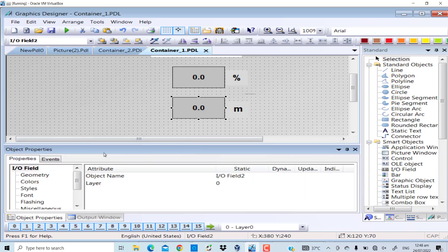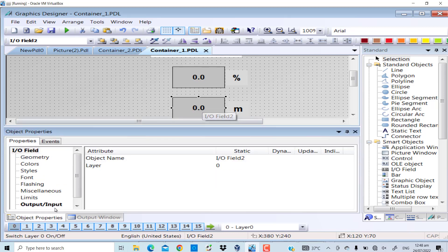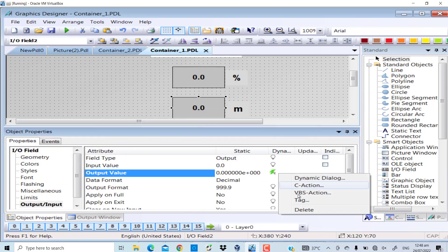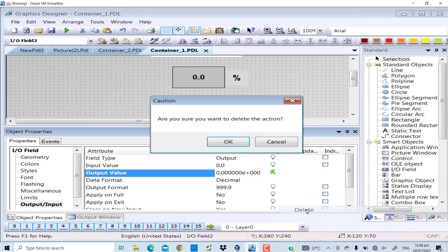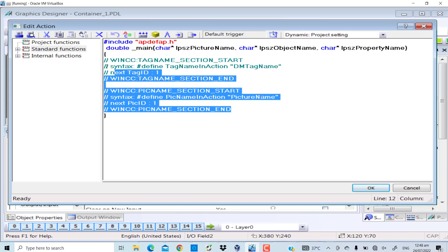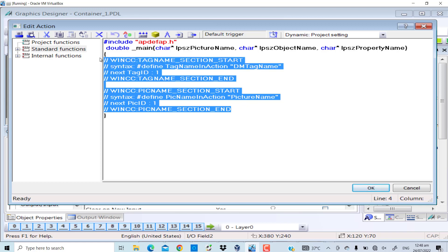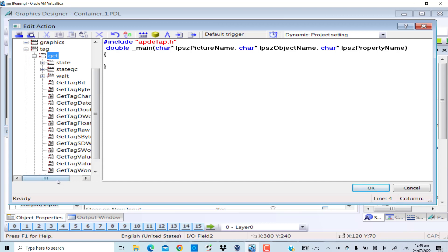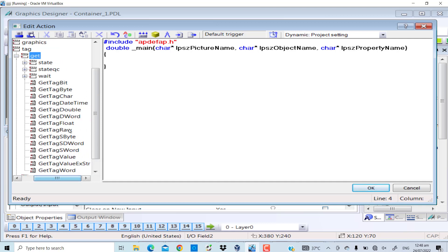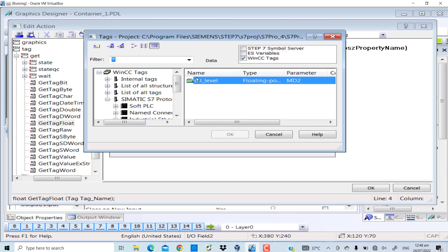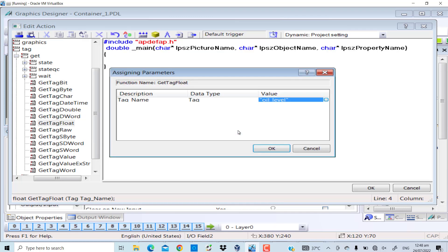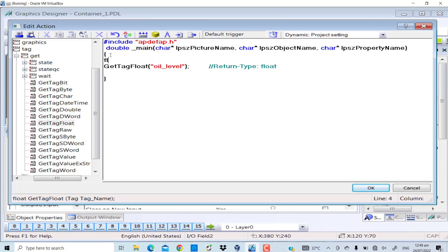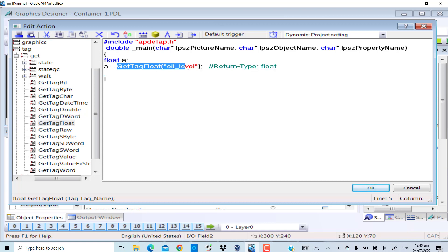Go to the properties of this IO field, delete script, C action. Go to the internal functions, tag, GetTagFloat. Oil level, good. Float a, and I will assign the GetTagFloat function return value to a, and in the end I will return a.